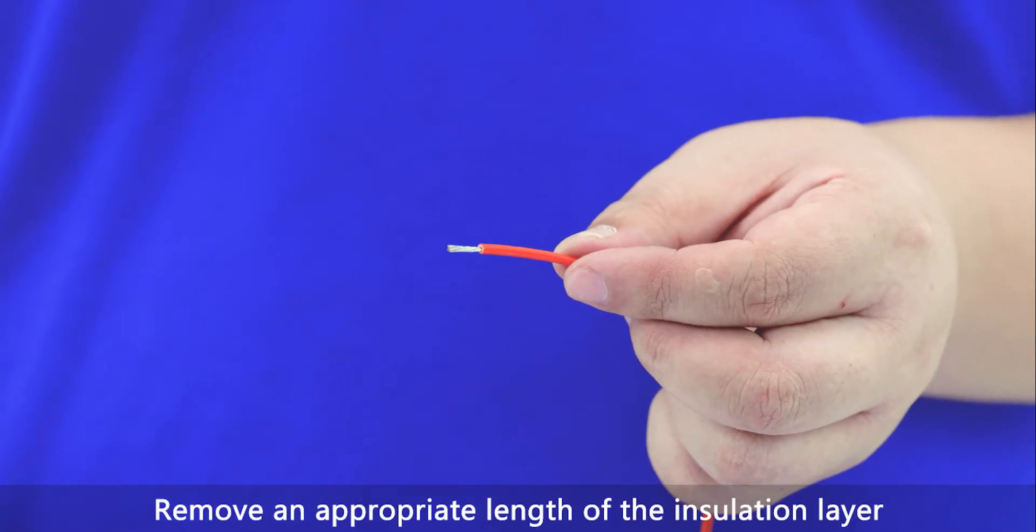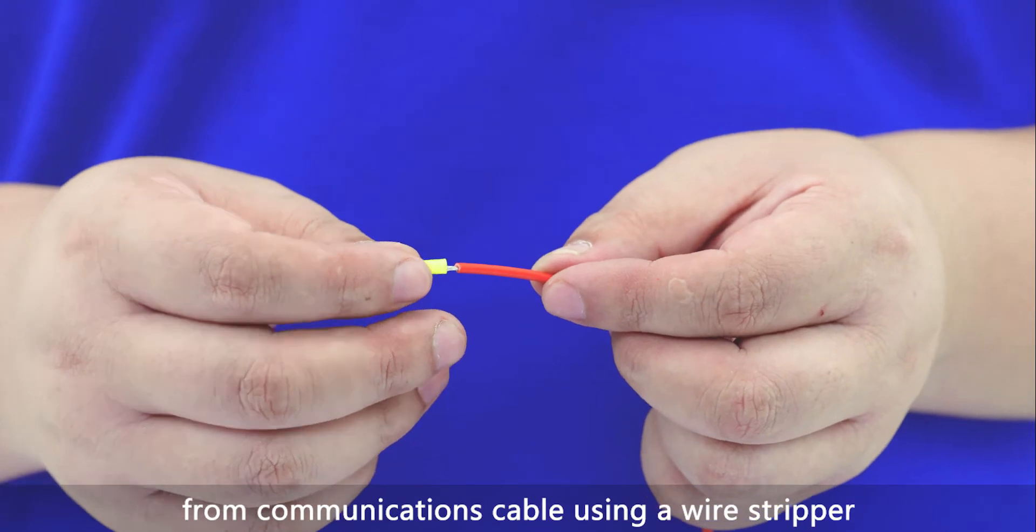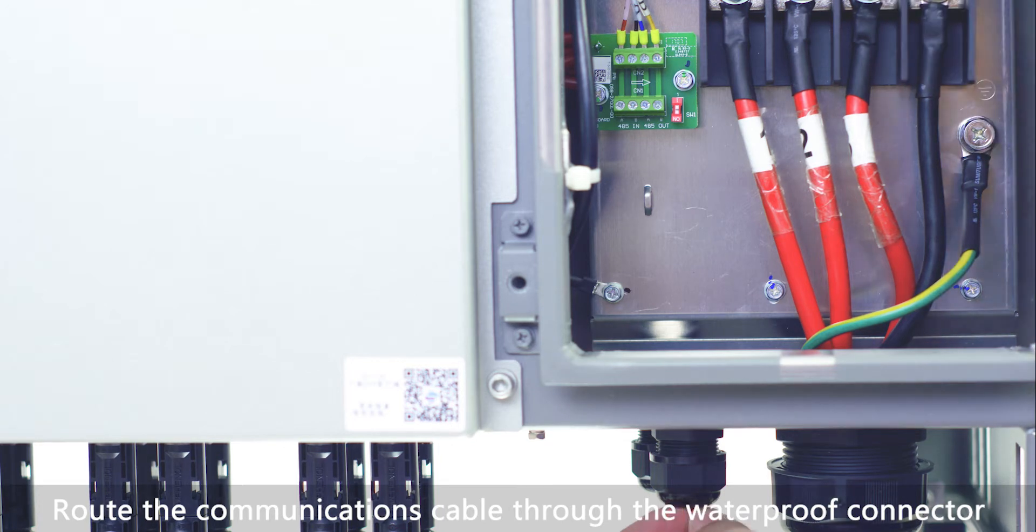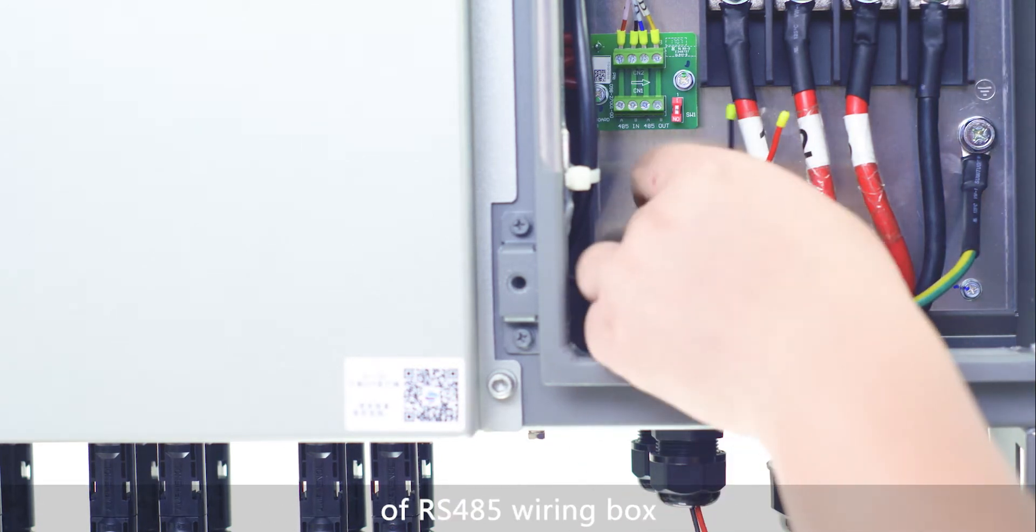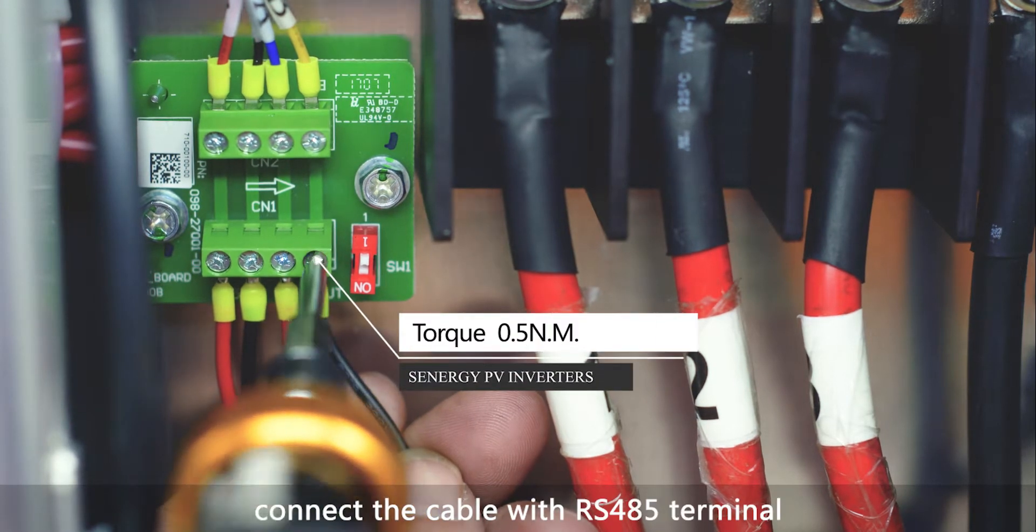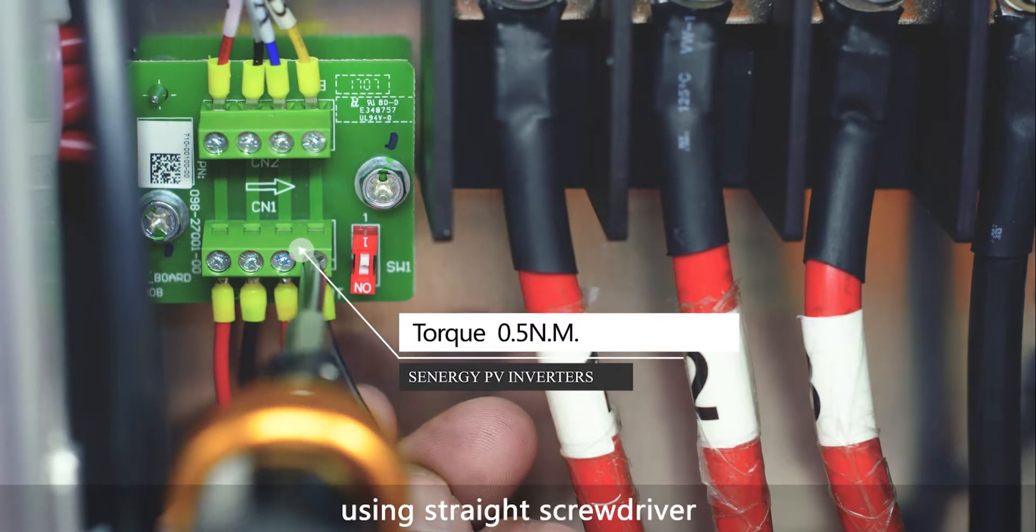Remove an appropriate length of the insulation layer from communications cable using a wire stripper. Route the communications cable through the waterproof connector of RS-485 wiring box. Connect the cable with RS-485 terminal using straight screwdriver.